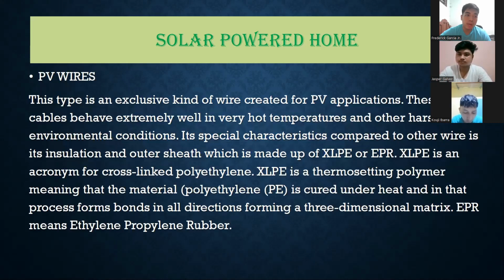Now we have PV wires. This type is an exclusive kind of wire rated for PV applications. These cables behave extremely well in hot temperatures and other harsh environmental conditions. Its special characteristic compared to other wire is its insulation and outer sheath, which is made up of XLPE or EPR.